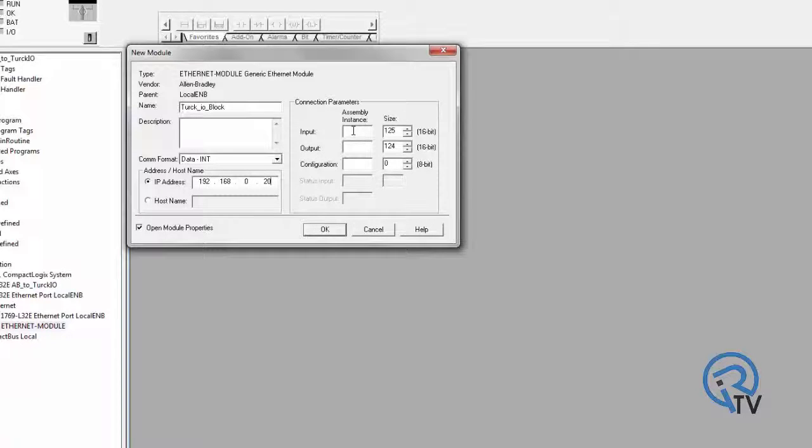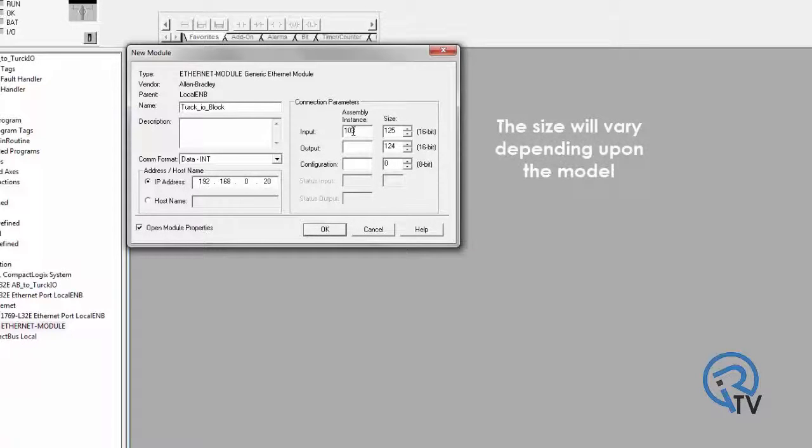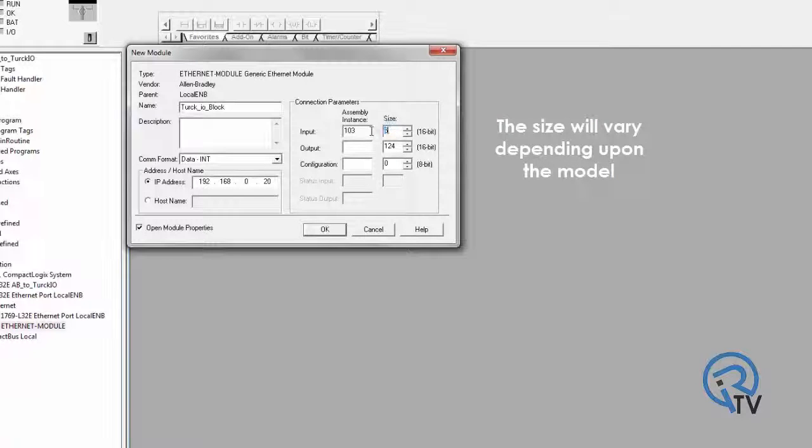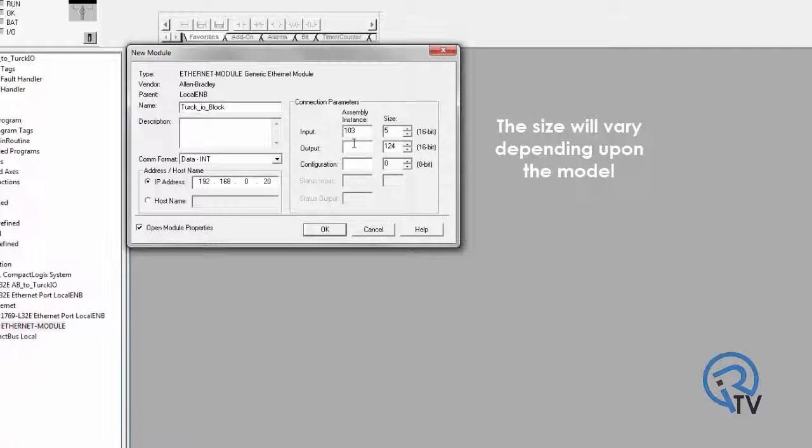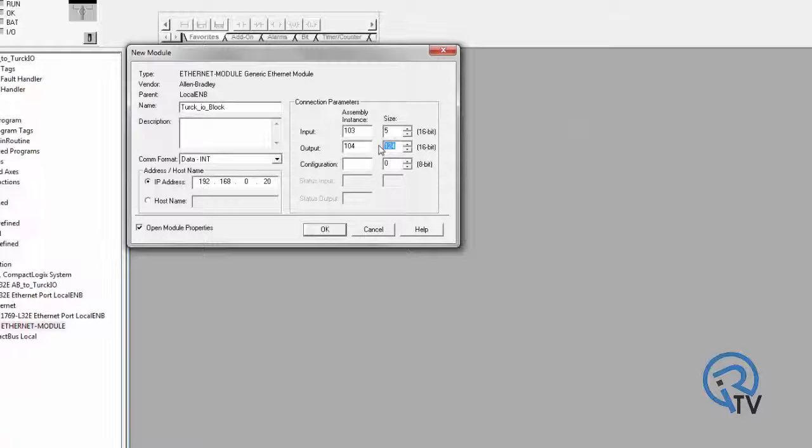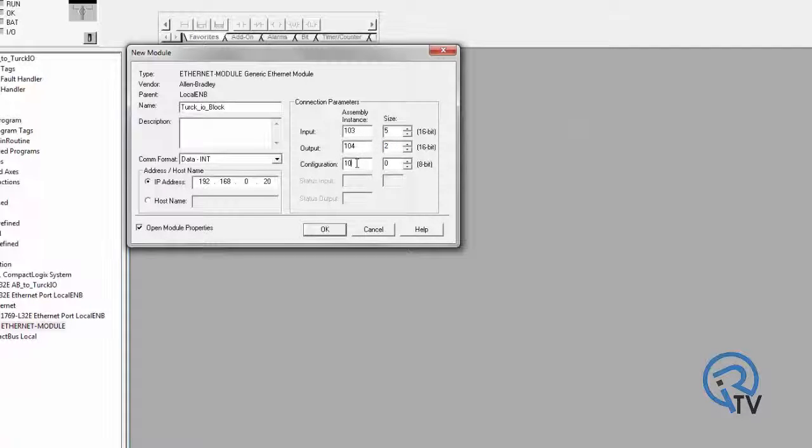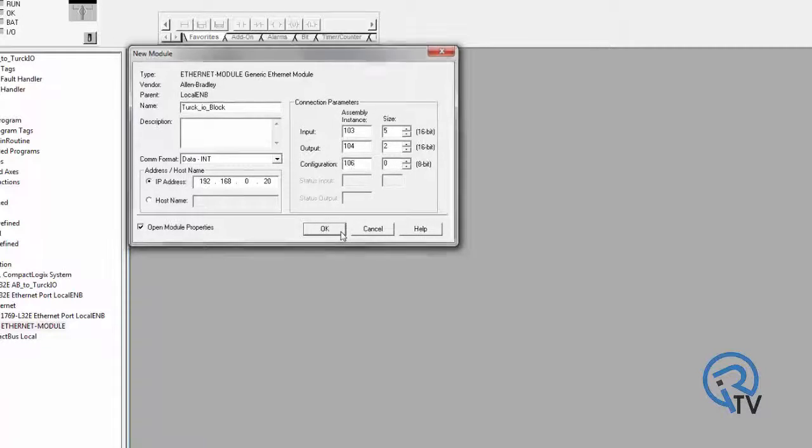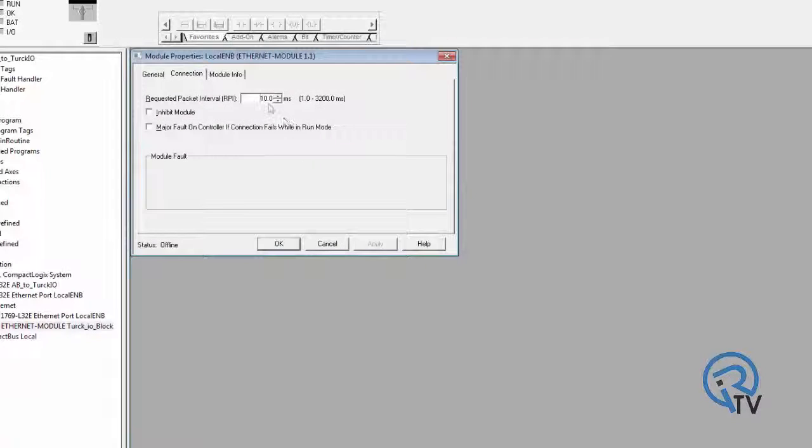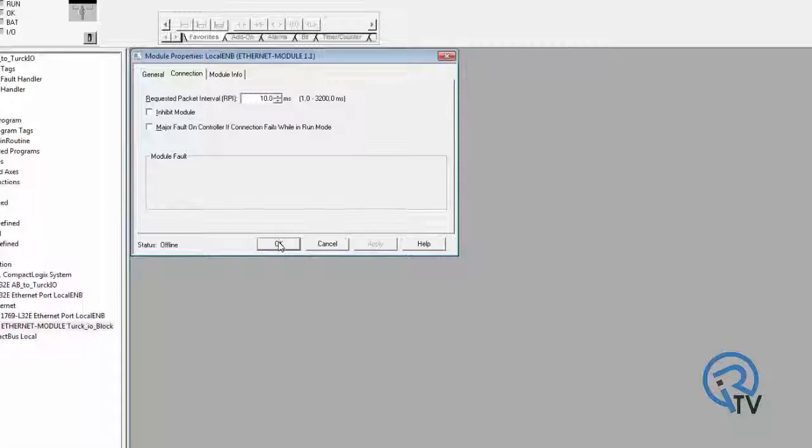Enter in 103 for the assembly input instance with a size of 5 and 104 for output instance with a size of 2. Configuration will be 106, 0 bits. And then leave the default with 10 milliseconds and press OK.